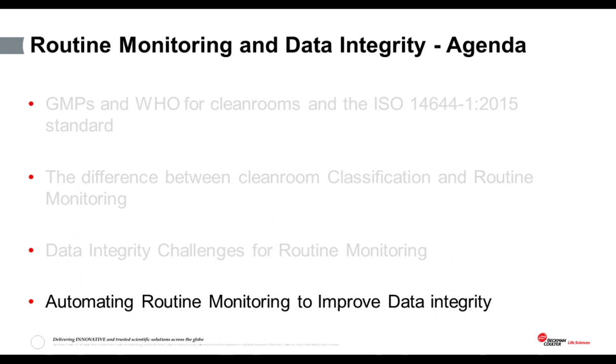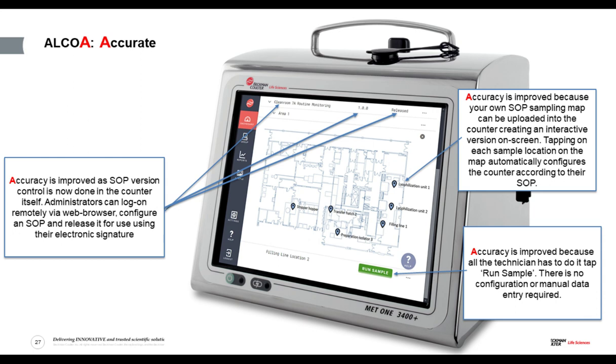Let's look at how we can automate our routine environmental monitoring programs to improve data integrity and reduce human error. With this particular particle counter on screen, accuracy is improved because the SOP sampling map from the site's SOP has been uploaded into the counter itself, creating an interactive version of the SOP sampling map. The technician follows the map to the next sampling location and simply taps on the location — the counter then automatically configures itself according to the SOP. There is nothing the technician has to do other than tap to run the sample; no manual configuration or manual data entry is required.